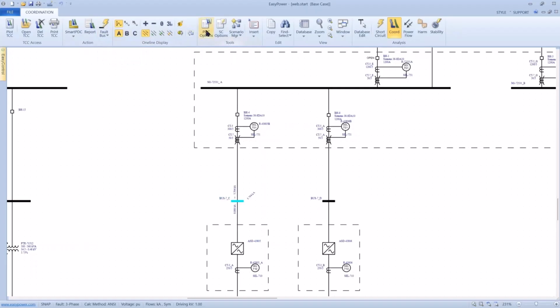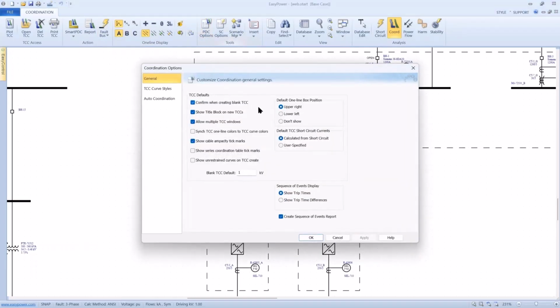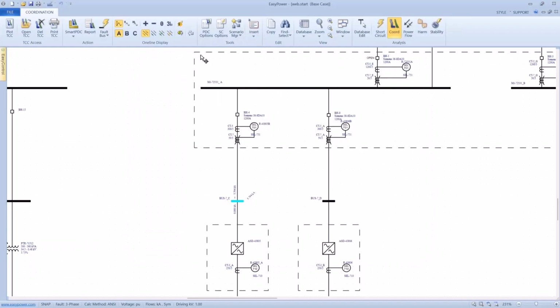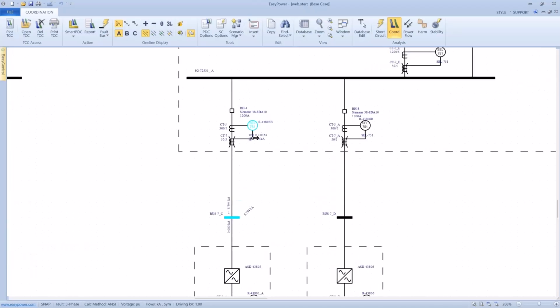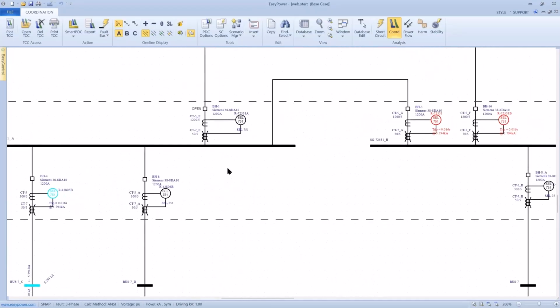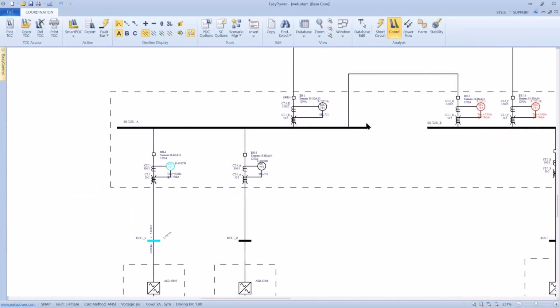Now before I do this, under my PDC options, in the right-hand column I've checked create sequence of events report. At the same time, the icon on the second row is made available to me when I'm in this condition. It not only demonstrates the sequence of events on the one-line, but it gives me a report that tells me something. So when this bus trips, this breaker will trip in 16 milliseconds. This relay will trip in 16 milliseconds. And so you can see I have miscoordination because apparently the relays haven't been set up.